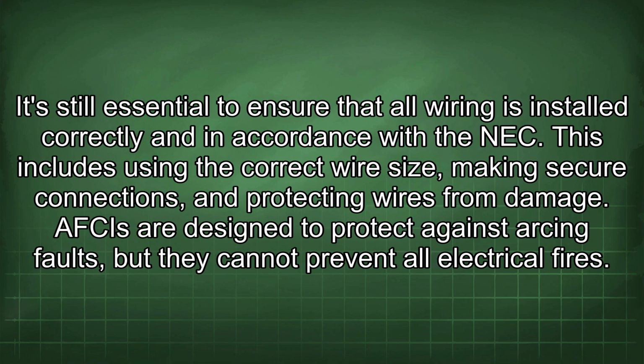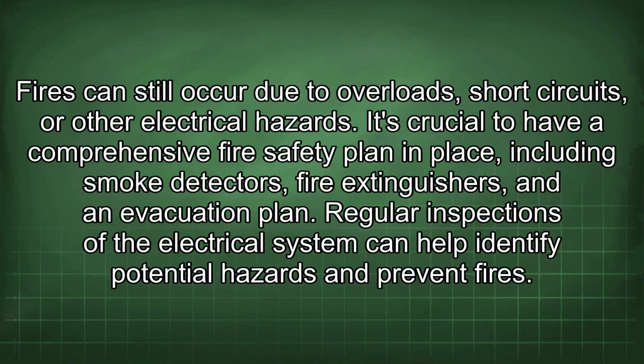It's still essential to ensure that all wiring is installed correctly and in accordance with the NEC. This includes using the correct wire size, making secure connections, and protecting wires from damage. AFCIs are designed to protect against arcing faults, but they cannot prevent all electrical fires. Fires can still occur due to overloads, short circuits, or other electrical hazards. It's crucial to have a comprehensive fire safety plan in place, including smoke detectors, fire extinguishers, and an evacuation plan.